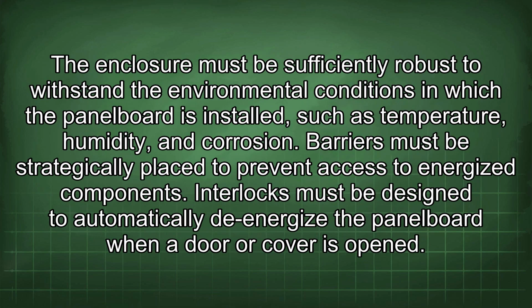The enclosure must be sufficiently robust to withstand the environmental conditions in which the panelboard is installed, such as temperature, humidity, and corrosion. Barriers must be strategically placed to prevent access to energized components. Interlocks must be designed to automatically de-energize the panelboard when a door or cover is opened.